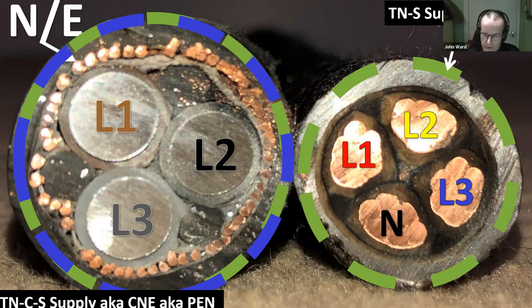So that's your SNE cable, separate neutral and earth. The one on the left is the newer type - only 3 conductors inside, and they happen to be aluminium conductors as well. So L1, L2, and L3 are inside. There is no neutral, but what's around the outside are individual copper wires, and those are used as the neutral and the earth. So it's all combined in the same conductor - that's CNE, or combined neutral and earth cable. Mainly used because, of course, it's much cheaper to make, since it's only got 3 conductors instead of 4.